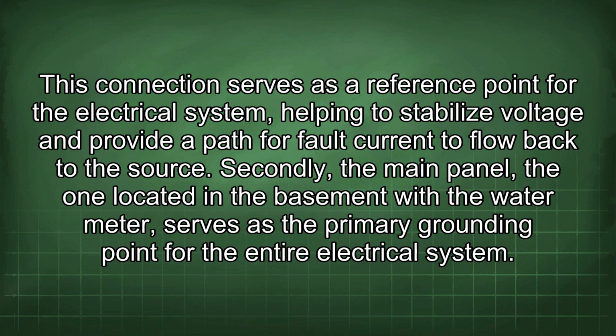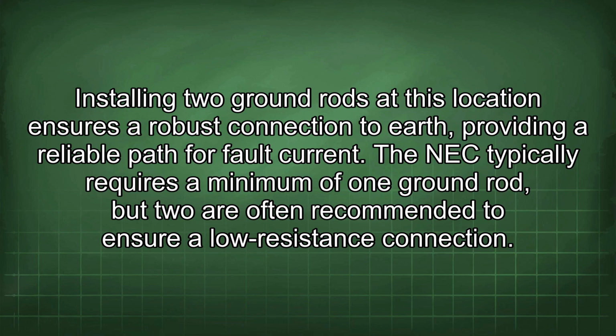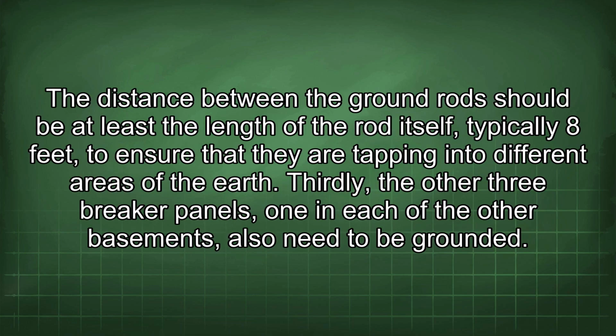Secondly, the main panel, the one located in the basement with the water meter, serves as the primary grounding point for the entire electrical system. Installing 2 ground rods at this location ensures a robust connection to earth, providing a reliable path for fault current. The NEC typically requires a minimum of 1 ground rod, but 2 are often recommended to ensure a low resistance connection. The distance between the ground rods should be at least the length of the rod itself, typically 8 feet, to ensure that they are tapping into different areas of the earth.